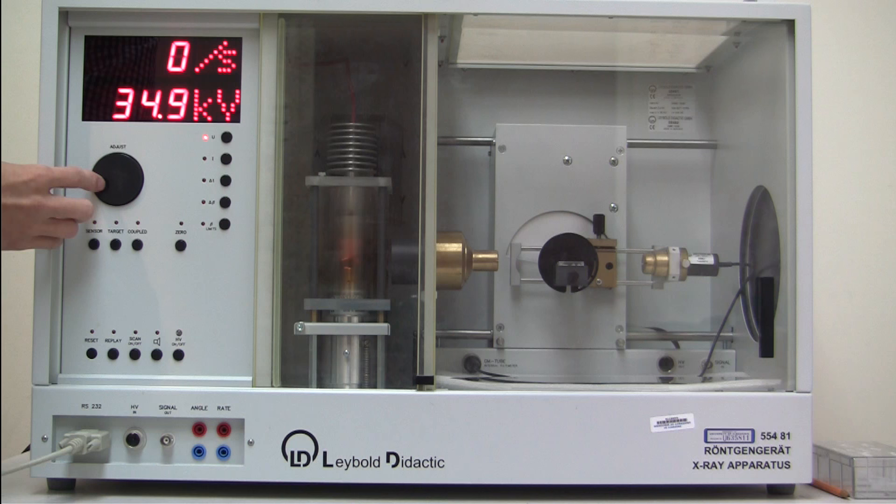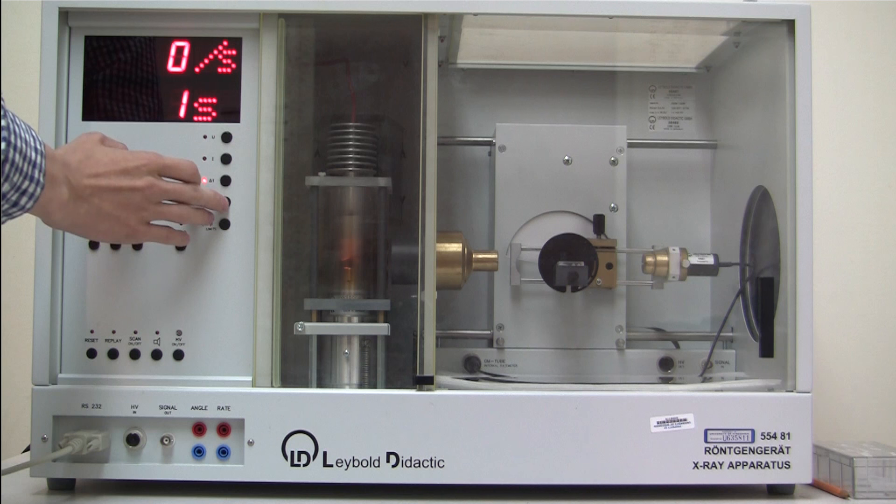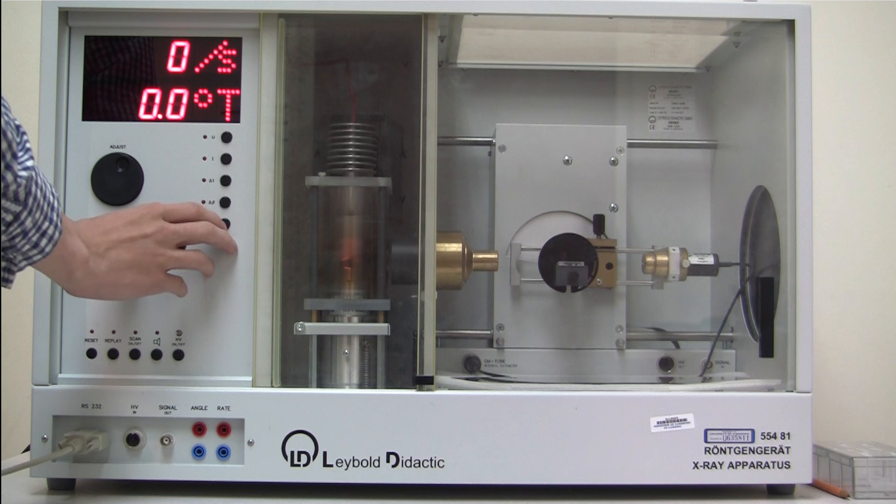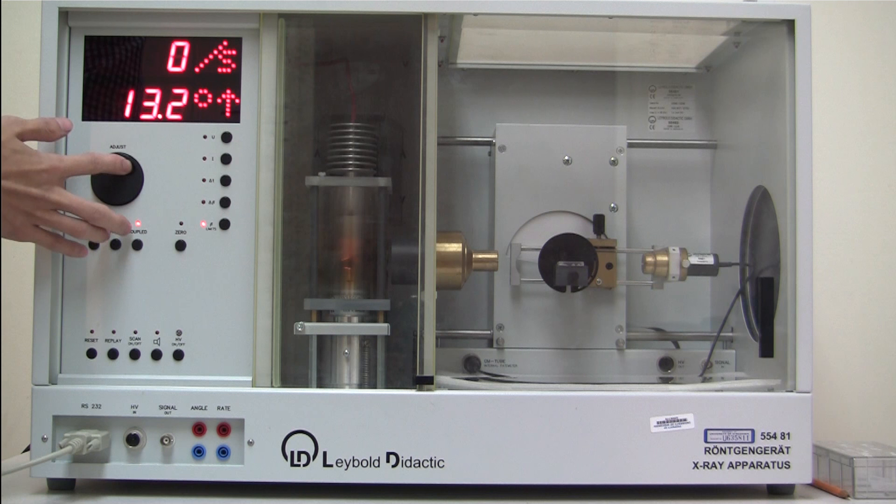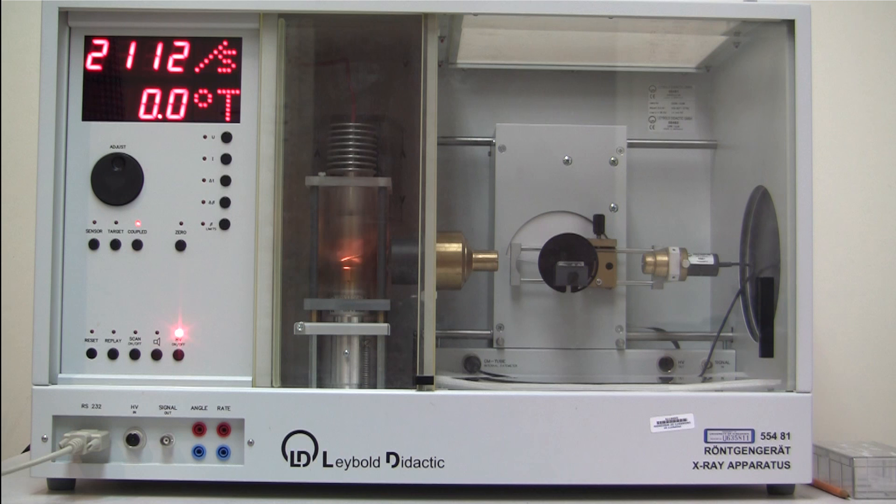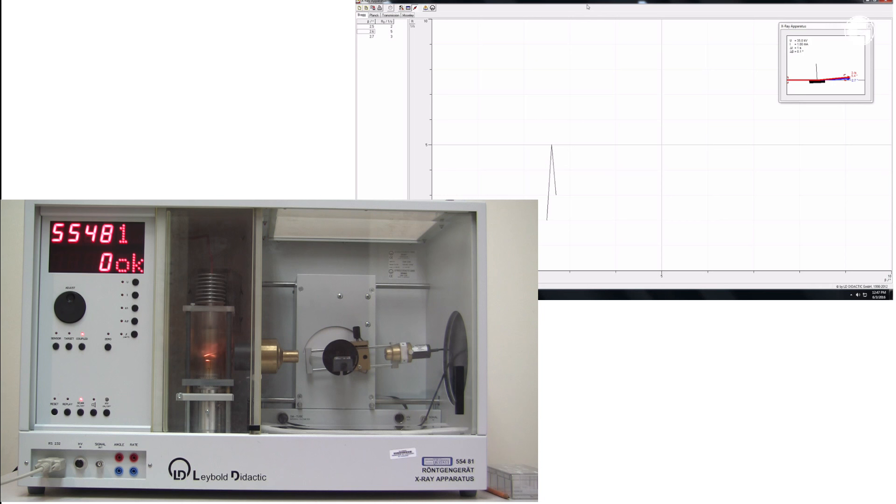Set the X-ray tube high voltage to 35 kV. Set the current to 1 mA. Set the measuring time per angular step to 1 second. And then set the angular step size to 0.1 degree. Press the coupled key to activate the electronic coupling of the target rotation and sensor rotation. Click on the beta limits key once for the lower limit and twice for the upper limit. Set the lower limit to 2.5 degrees and the upper limit to 10 degrees. Press the HV on/off button to apply high voltage. Then start the scan by pressing the scan on/off button.